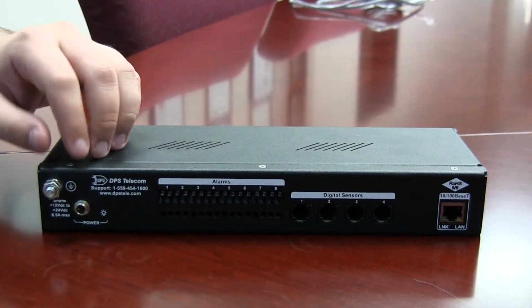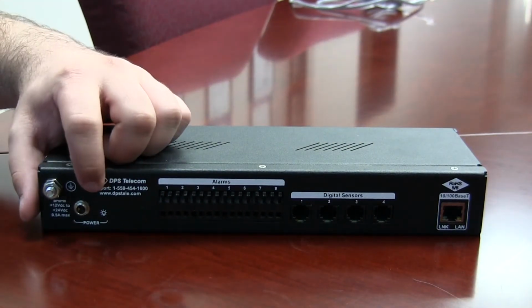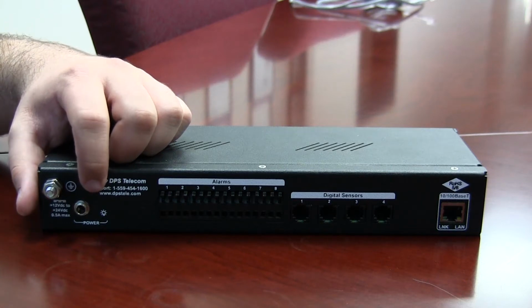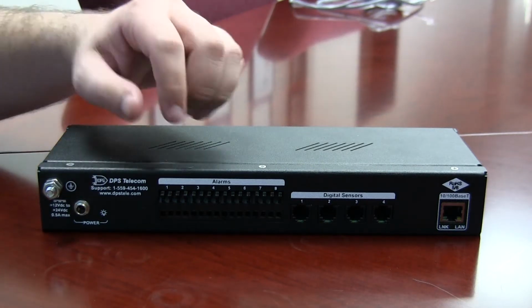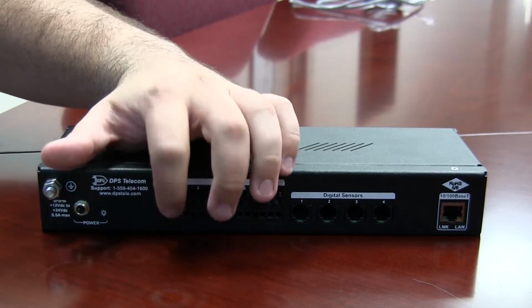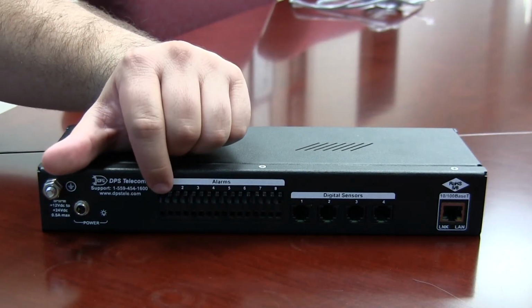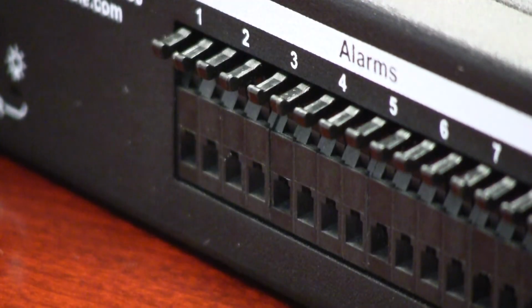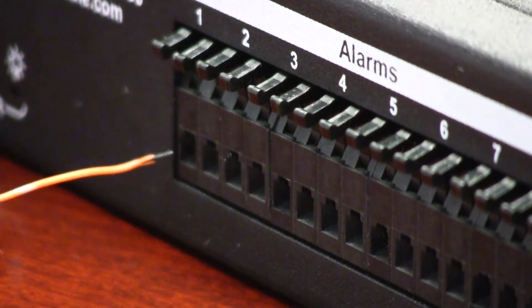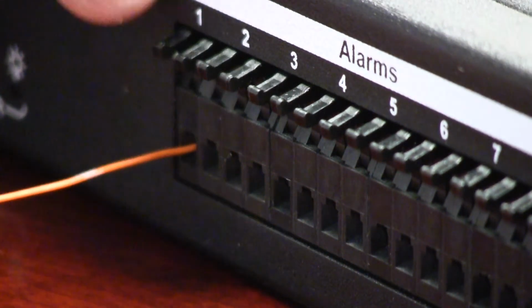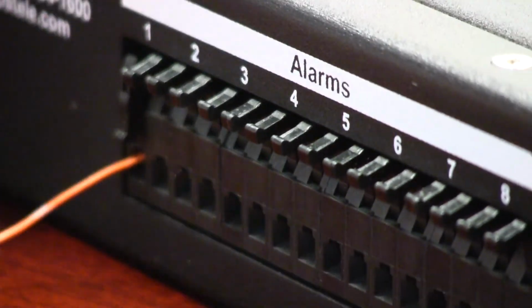Looking at the back panel now, you have a grounding lug, power input, which is available in a variety of different connectors. This is a barrel plug connector. Piano-style alarm termination, so you don't need any tools. Just strip a piece of the alarm wire, insert it into this hole, and then click the connector down to lock the wire into place.